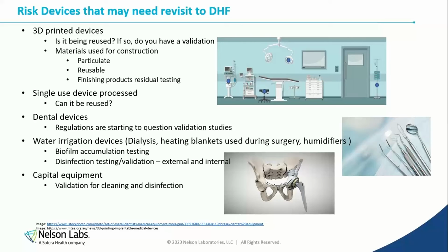Capital equipment, these are equipment that are just in the OR sitting on the side, helping devices that are used in critical procedures. They definitely need validations and have been for a couple of years, but we're seeing more and more. I just saw yesterday, I was down in the lab and I saw a huge monitor that's a touch screen, and they use it in the OR when they're putting devices in. Sometimes they touch those screens during surgery, and now you've contaminated that screen with blood. Now, how are you cleaning that off? That is the manufacturer's responsibility to address that question.